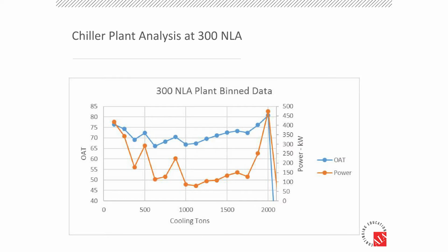So here's the bin data. This is how the power matches with outside air temperature and tonnage. But until we could actually see, so when we put in the central plant optimization routine, we were able to start seeing interval data down to the minute level. We realized minutes probably a little too fast. The pumps don't even react. Water can't get around the building. So we started looking at it at 15-minute and then hourly data.